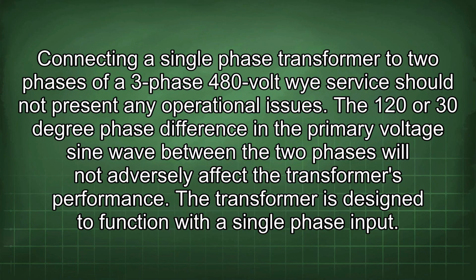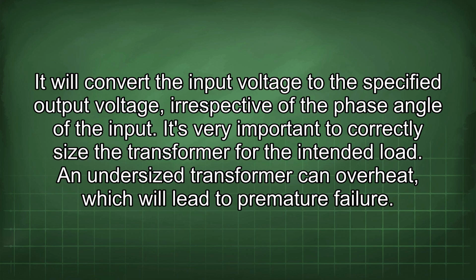Connecting a single-phase transformer to two phases of a three-phase 480-volt Y service should not present any operational issues. The 120 or 30-degree phase difference in the primary voltage sine wave between the two phases will not adversely affect the transformer's performance. The transformer is designed to function with a single-phase input. It will convert the input voltage to the specified output voltage, irrespective of the phase angle of the input.